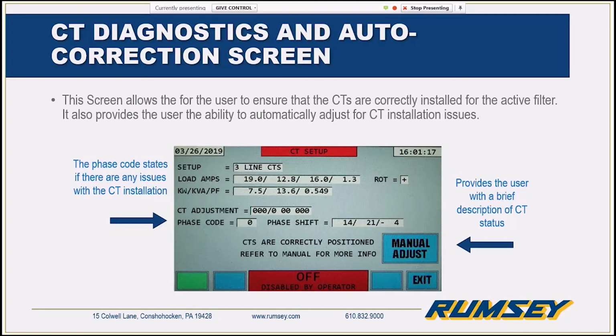We must have already been working on this at the time, I guess about 5 years ago. Our engineer went out there, flashed the unit, and it was able to determine that 2 CTs were on the line side, 1 was on the load side, and 2 of them were flipped the wrong way. An option of error we hadn't even thought about, and the unit was able to automatically adjust for that, so they didn't have to take it apart. So again, extremely powerful tool.